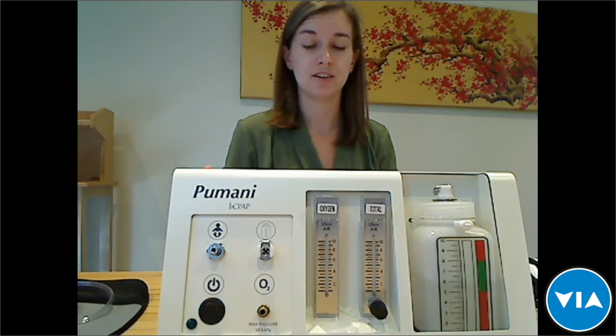Great. And what are the key differentiators for the Pumani, for why someone should buy this machine and not another competitor? Yeah, so the Pumani is one of the only CPAP devices, and I would say the only CPAP designed for Africa specifically, that actually has an air compressor inside of the machine. As surprising as that is, most CPAP devices do not have an air compressor. In US hospitals, for example, typically there's piped compressed air and piped oxygen, and CPAP systems are attached to this piping system, and that is delivering the CPAP. But as you may know, in many African hospitals, low-resource hospitals, this piped air and piped oxygen is not available, and so you need a CPAP that has that compressed air. And so the Pumani provides that compressed air in a very effective and affordable way.